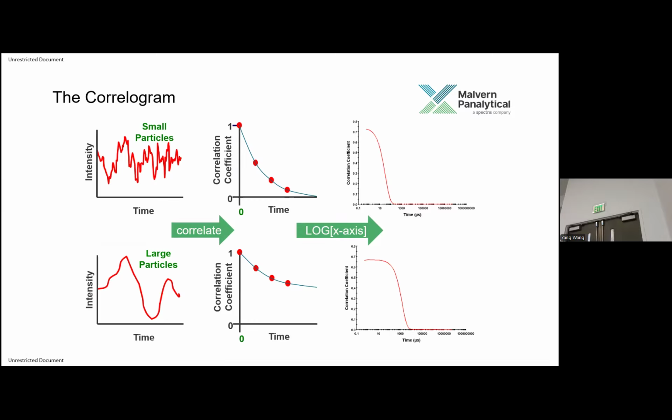And sometimes, just along that point, if you've got very large particles but at lower concentration, they might present as number fluctuations. Meaning that if you're looking at your scattering volume within the cuvette, you might have large particles popping in and out of the scattering volume, offsetting your count rate of photons, and how that will present is a nonsensical y-intercept. As we just said, the theoretical limit is 1, and it'll present a y-intercept that's above 1, and that's often coupled with a raised or a noisy baseline at the end of your correlogram. Okay?